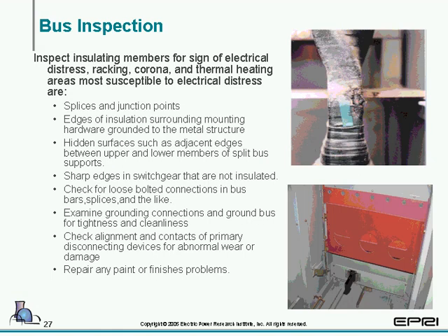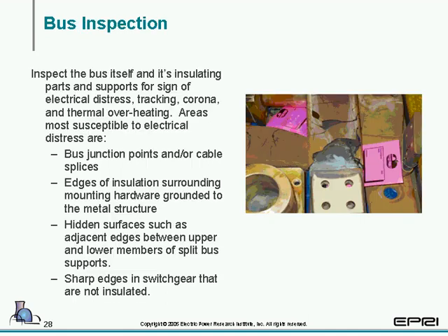That pretty much ends cubicle. Now we take a look at bus inspection. Again, we're going to take a look at inspection, cleaning, and then testing. We'll start off with bus inspection. First thing we want to check is the insulating or insulation parts. And we have a list. We'll look for splices, edges of the insulation, hidden surfaces, and such.